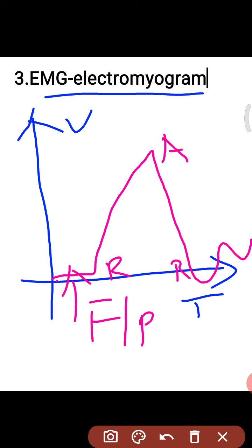The action potentials are generated both positive as well as negative. This is the positive waveform and this is the negative waveform. Your muscle contracts, and again it relaxes after leaving the force. In this case both polarities appear across the pair of electrodes, so sometimes they add and sometimes they subtract. The electromyogram signals range from 20 microvolts to 5 millivolts, and the frequency ranges from 10 hertz to 2 kilohertz. This method is suitable for use in hospitals.